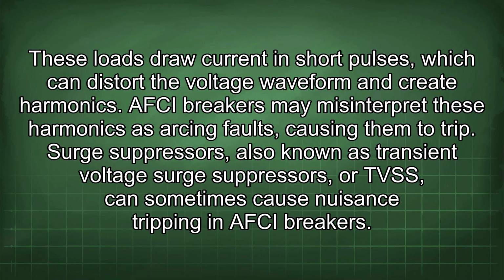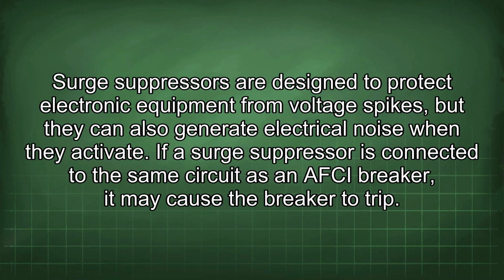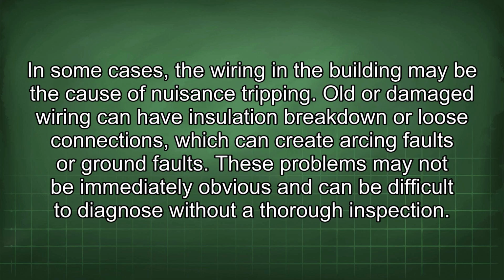Surge suppressors, also known as transient voltage surge suppressors, or TVSS, can sometimes cause nuisance tripping in AFCI breakers. Surge suppressors are designed to protect electronic equipment from voltage spikes, but they can also generate electrical noise when they activate. If a surge suppressor is connected to the same circuit as an AFCI breaker, it may cause the breaker to trip. In some cases, the wiring in the building may be the cause of nuisance tripping.